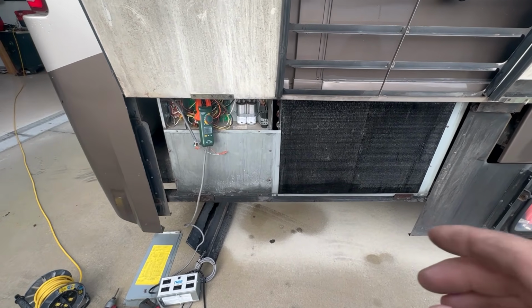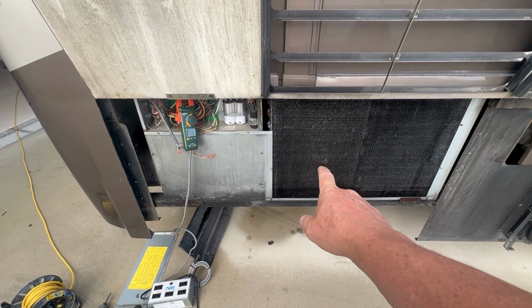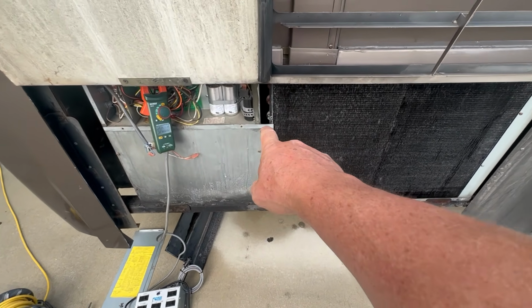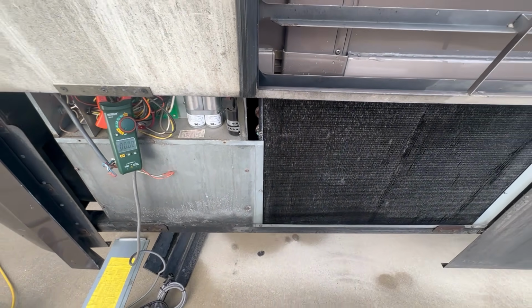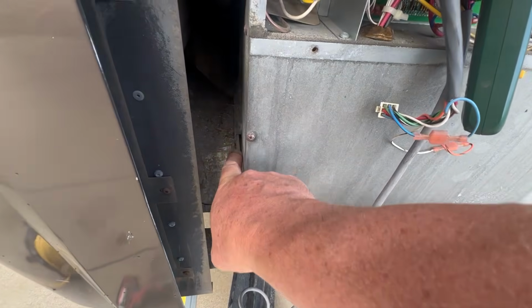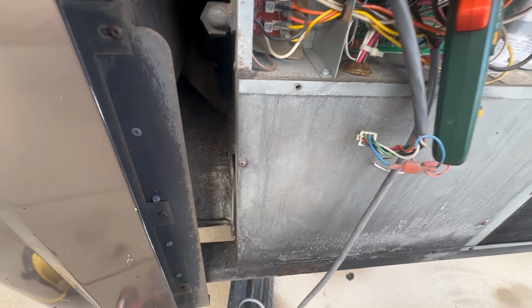Let's go over here and take a look at it because I've got it running, and we'll take a look at some amp draws. I had this unit running for a couple minutes, and circuit 2 is an amp higher than circuit 1. I can look inside there and see one of the lines is froze up, and we've got some air leaking tremendously out of that right there.